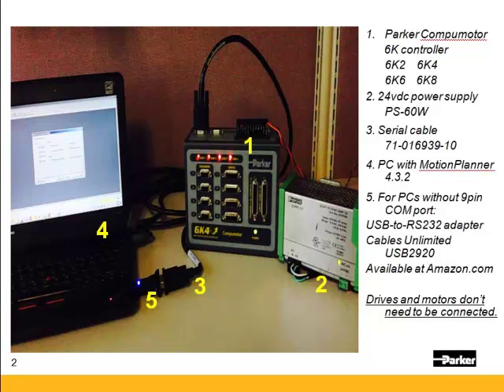Not all USB serial adapters work the same. If you aren't using one with the FTDI chipset it may or may not work. Note the prolific chipset does not work on Windows 7. It does work on XP. You do not need the drives or motors to be connected to upload and download.